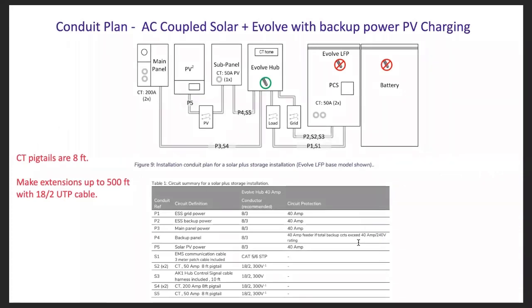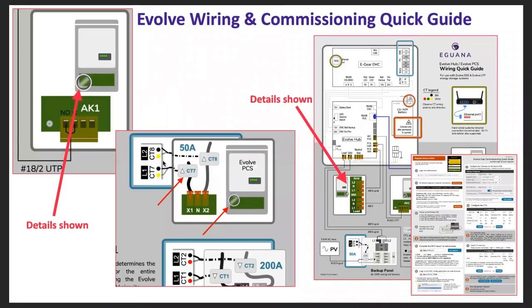Here is another view of that block diagram with the conduit schedule on here. I won't get into too much detail on this again, but just to note, the CT pigtails on the CTs that come with each system are 8 feet. While they can be extended, they can be extended up to a maximum of 500 feet with the right spec cable or wire. These little details are taken from the wiring and commissioning quick guide.